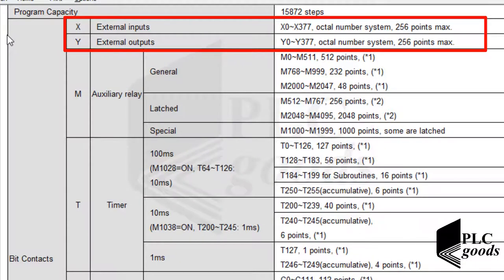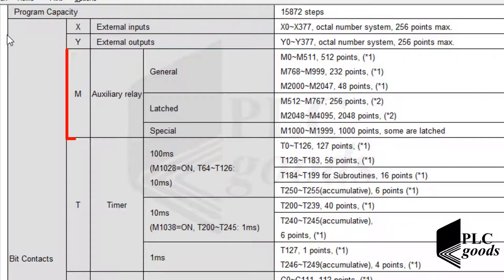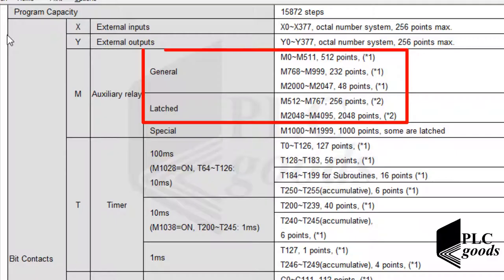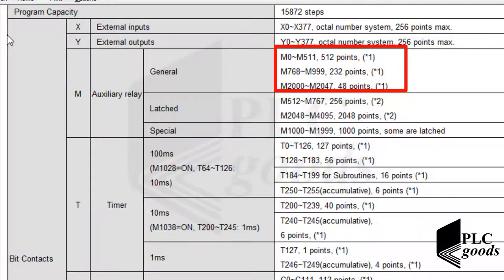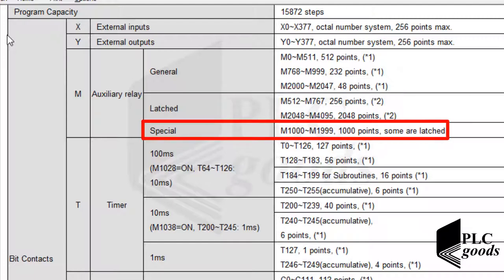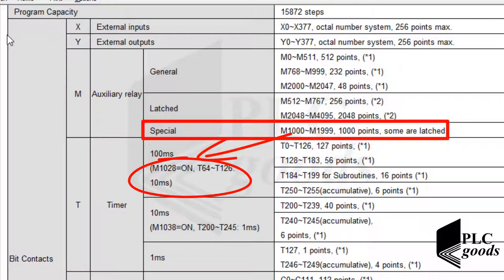Now pay attention to the bit contacts section. We use X and Y letters for external inputs and outputs, and the letter M for auxiliary relays inside the PLC memory. There are three types of auxiliary relays: general, latched, and special. The main difference between general and latched is what happens when power is disconnected — general bit memories lose their last state and reset to 0, but latched memories retain their state. Special memory addresses are used for specific tasks; for example, if a certain memory bit changes to 1, timers from T64 to T126 will work at 10 milliseconds instead of 100 milliseconds.